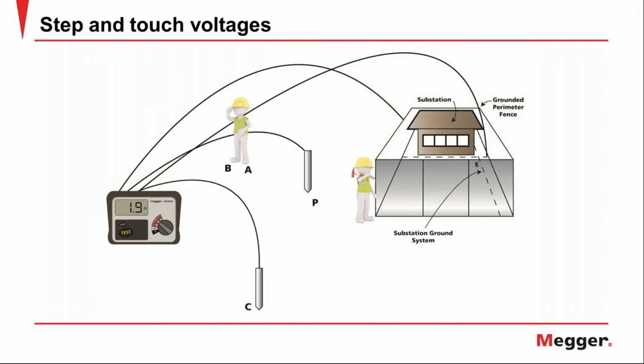So note here, what happens if somebody walking by were to touch the fence, and it's while the substation is in effect clearing a fault somewhere out on the line? Well, that current is flowing back to the substation through the earth. And so your touch potential would be a person touching the fence. Step potential would be the voltage that can develop between your feet, or about 3 feet.